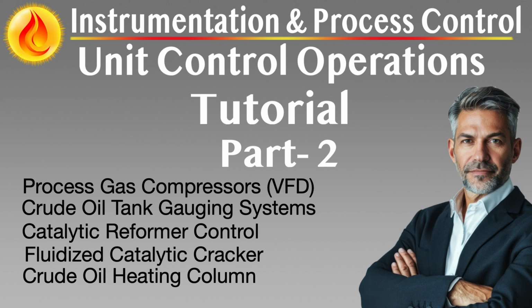Suction pressure control is particularly important in LP systems where upstream production, e.g. gas recovery, vent gas, or flash gas, can vary significantly. A PID controller adjusts the VFD speed to maintain suction pressure within limits, absorbing fluctuations without triggering recycle or flare events. Surge control is a top operational priority for dynamic gas compressors.